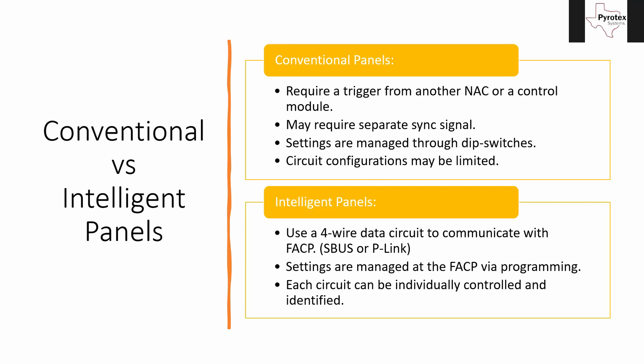Another cool thing about SBUS and PLINK: they can be T-tapped. With Class B supervised circuits — like a NAC circuit or a speaker circuit — if you want to add a device in the middle, you have to pull a send and return wire over to it; you can't just pull one wire because you have to interrupt the signal path to keep it fully supervised. But with intelligent circuits like SLC, SBUS, and PLINK, you can T-tap it because every device is supervised at its unique address. This can cut the amount of wire in half, especially getting SBUS from one end of a school to the other.